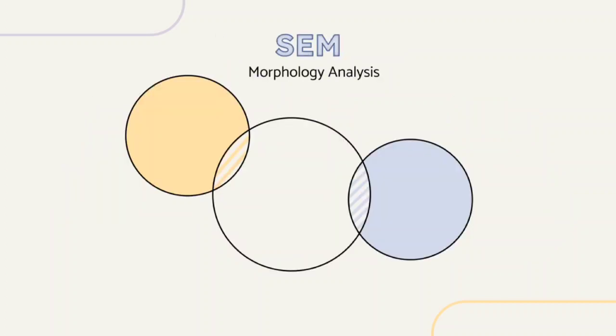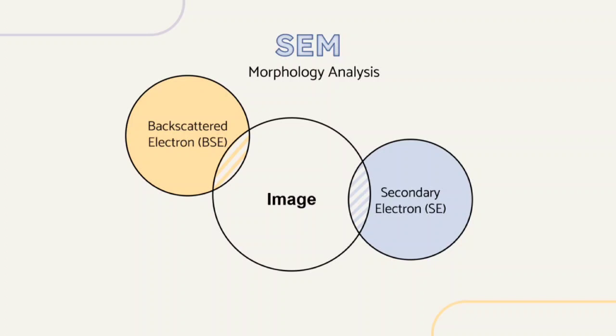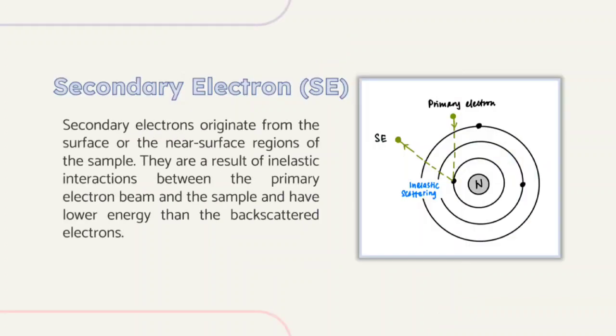SEM undergoes morphology analysis through two imaging modes: secondary electron, SE, and backscattered electron, BSE, where these two imaging modes work by collecting emitted electron signals from a sample. Secondary electrons originate from the surface or near-surface regions of the sample. They are a result of inelastic interactions between the primary electron beam and the sample, and have lower energy than the backscattered electrons.